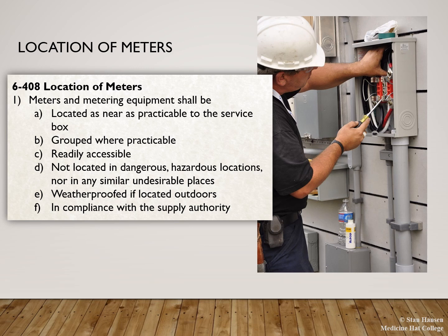Also, places like Medicine Hat, Brooks, and Calgary have a rule where the center of the meter base must be within 1800 millimeters and 1500 millimeters from the finished grade. So typically speaking, we would want to place our meter within those 2 measurements from wherever the tar line is on the foundation.